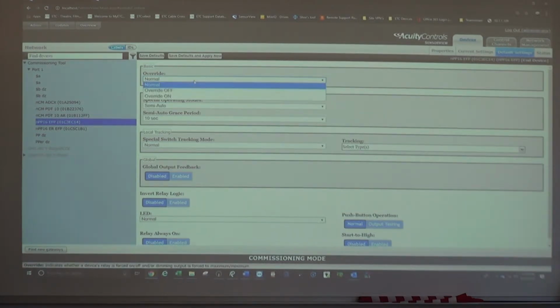If you change the default setting to override on, it's going to be manual and will only respond to a switch. It won't respond to a power pack, because you're overriding its function. Make sense? There's no reason to, I'm just explaining what the override actually means, because a lot of people change it.